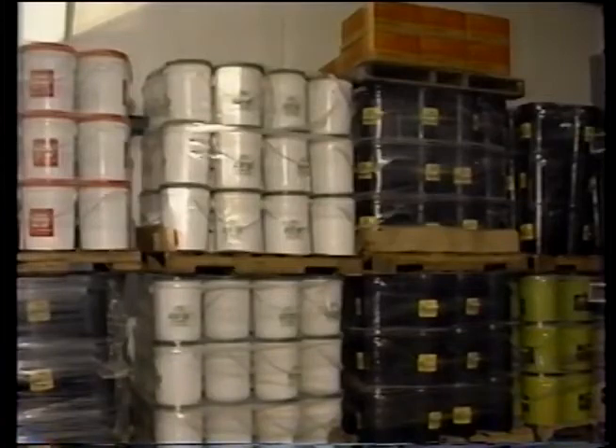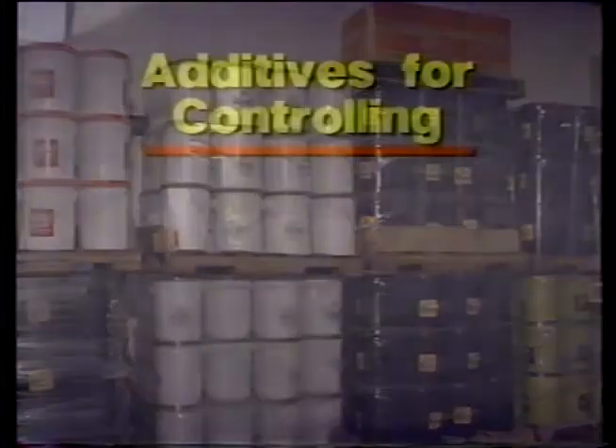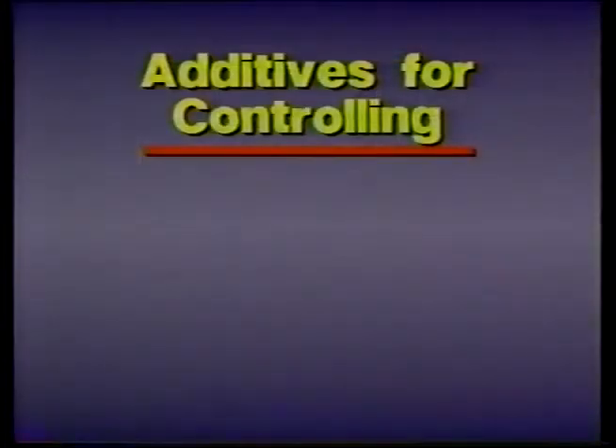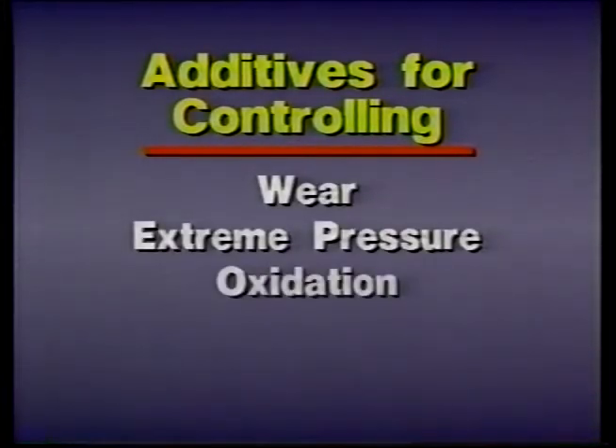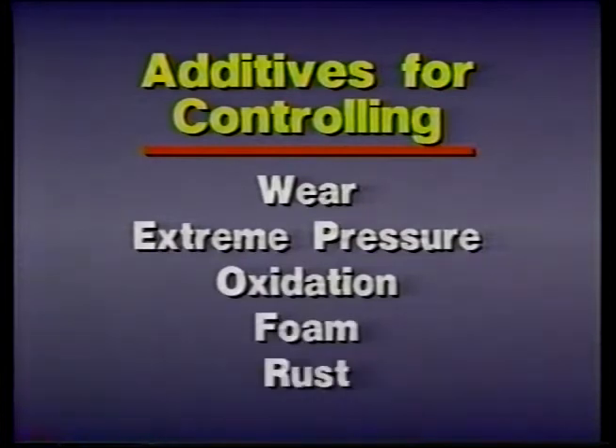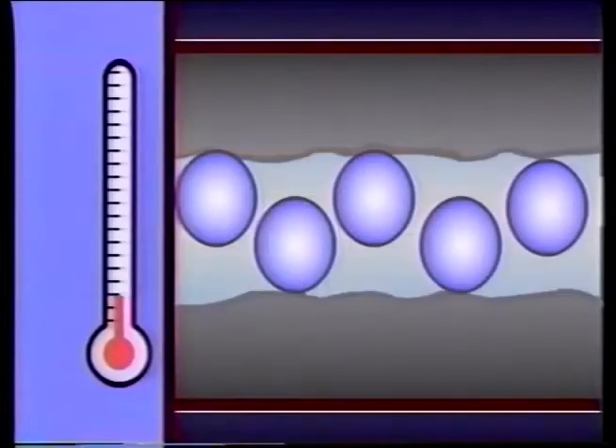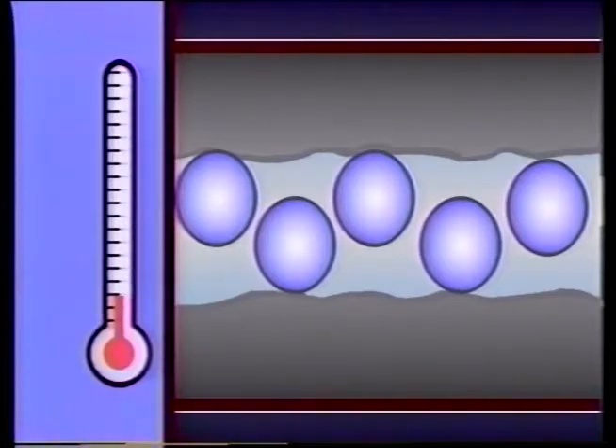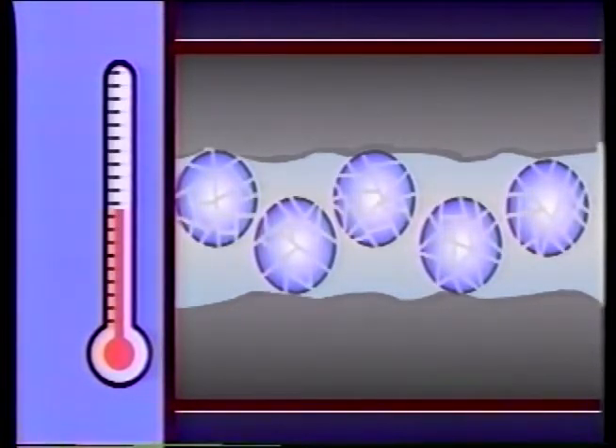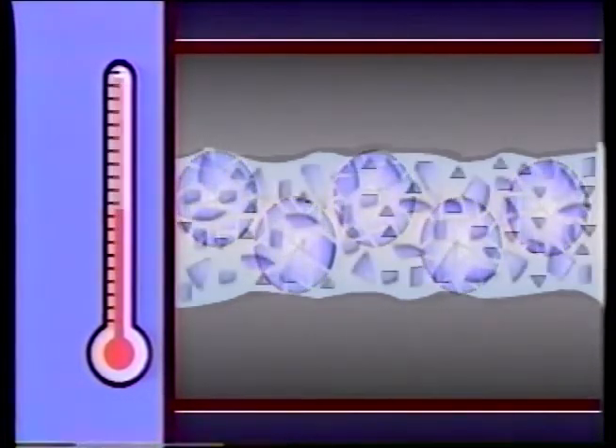As industry's use of hydraulics has expanded over the years, a variety of chemical additives have been developed to handle problems of excessive wear, extreme pressure, oxidation, foaming, and rusting. Several kinds of anti-wear additives are available. One common type works by increasing the lubricity of the fluid — the molecules in the additive form a film which helps to keep the surfaces apart. Unfortunately, this kind of additive has a limitation: it tends to break down at high temperatures.